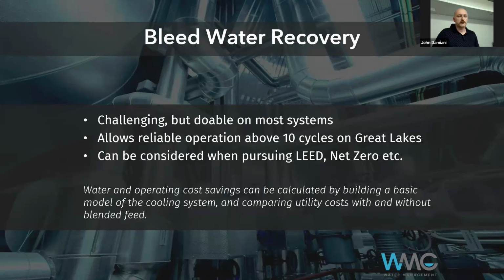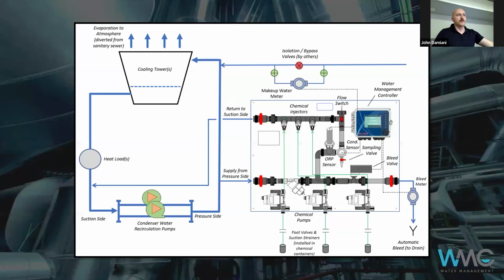Another form of wastewater recovery is bleed water recovery. With a cooling tower system like the one shown, it might sound counterintuitive—why recover water we're deliberately bleeding out to replace with fresh makeup? But if you treat it to a certain level, you can recover it, and treatment systems exist to achieve that, with really good paybacks. This is a higher cost compared to the soft water makeup we discussed, so it depends on the system and your goals, but if you're pursuing water efficiency, it's definitely worth considering.